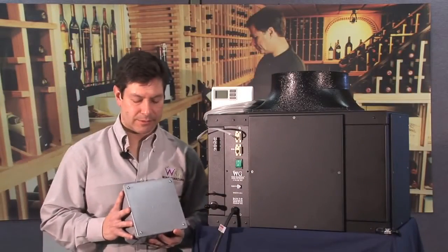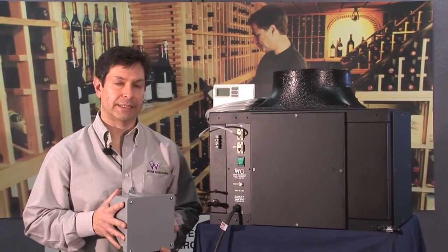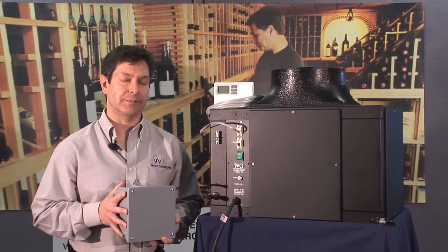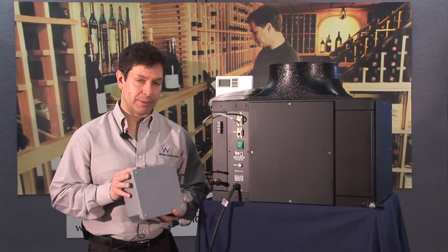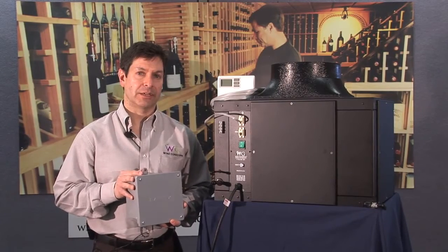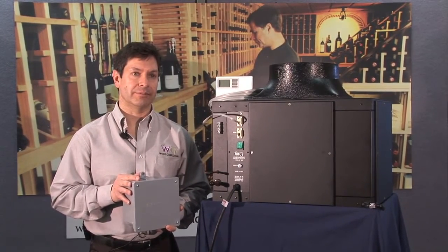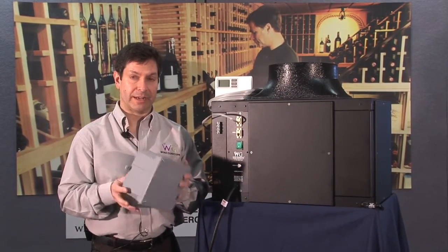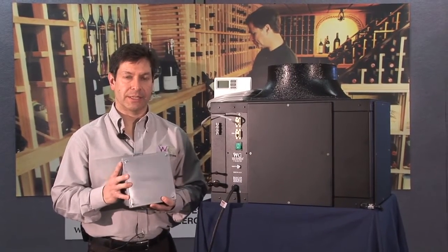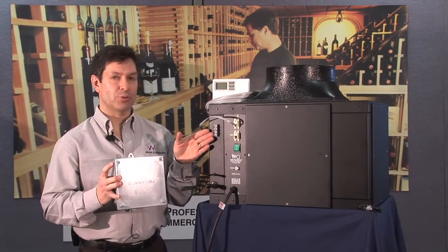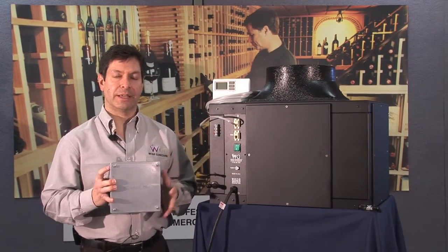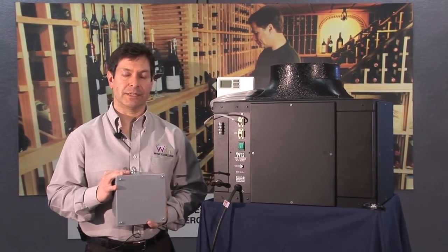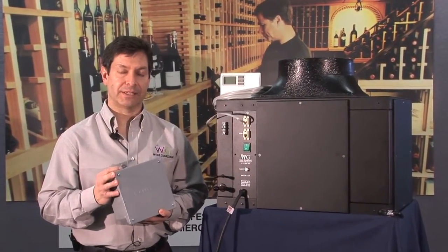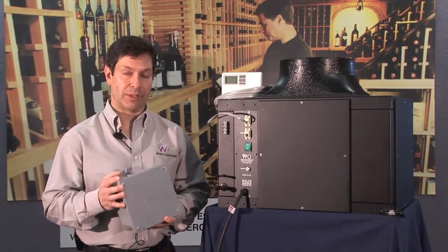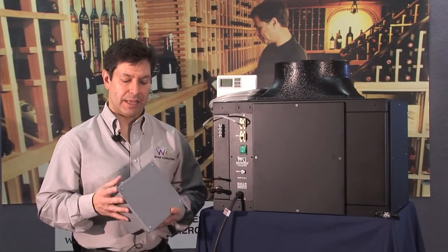The 24 volt contactor control box is supplied with the split system from Wine Guardian. So you will be supplied with this control box that should mount in close proximity to the condensing unit in an outdoor enclosure as we've provided here. And essentially this is the control box which will take your 24 volt from your fan coil unit and your primary power to your condensing unit. So you want to make sure that you have this and have located it. It should have been supplied with the Wine Guardian split system, and you will need this for proper installation.